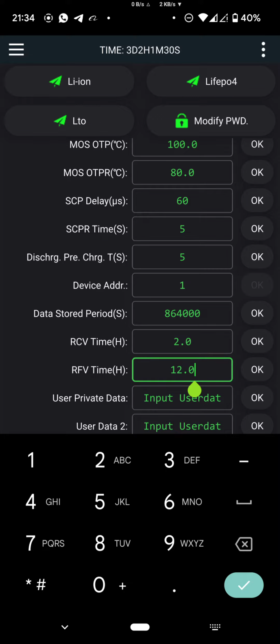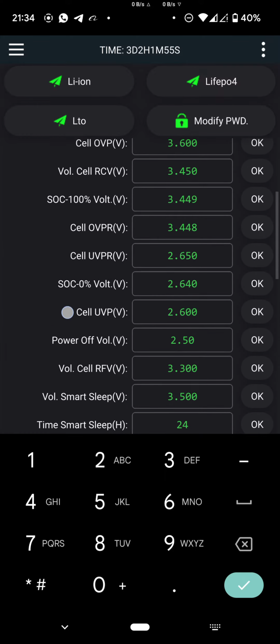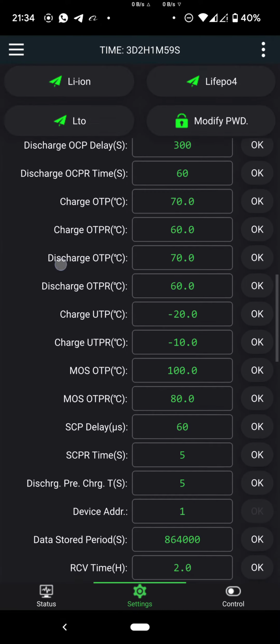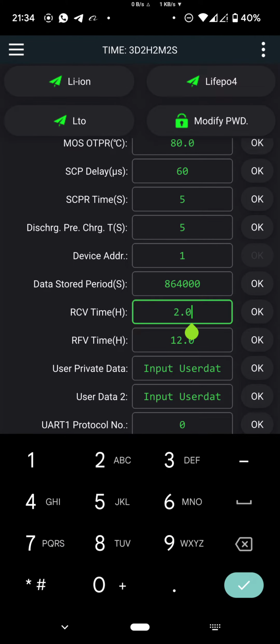RCV time in hours and RFV time in hours. These two are also new parameters related to the floating feature that was introduced in the new firmware. As far as I know, the way it should work is after the SOC 100 value is triggered, as set in the above parameter here. If it is triggered, the BMS should keep requesting the RCV, which is the charging voltage of 3.45 times 16 for this many hours, in our case 2 hours.